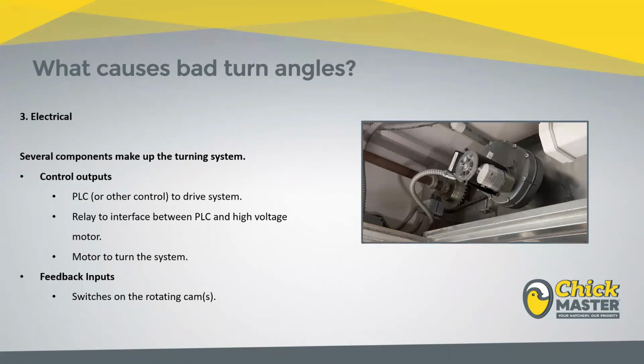But in order to do that, you also need feedback from those limit switches, which tell the control where it is. So if your turning system isn't starting for whatever reason, you want to be starting at the top of that list, your PLC, to ensure that it's giving that signal out. And then work your way down the list to make sure your relay is activating, and that it's giving a high voltage, and then to see whether your motor's turning or not. And on this picture, you can see a capacitor on the motor. 9 times out of 10, if your motor's not turning, you're going to find out that it's either the relay that's gone or it's that capacitor.